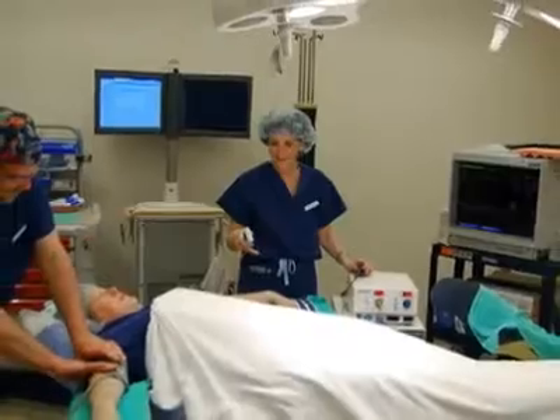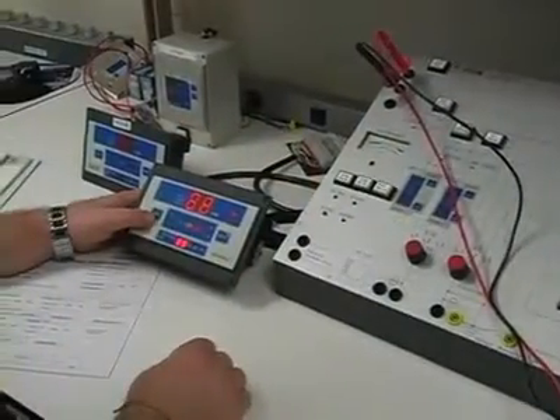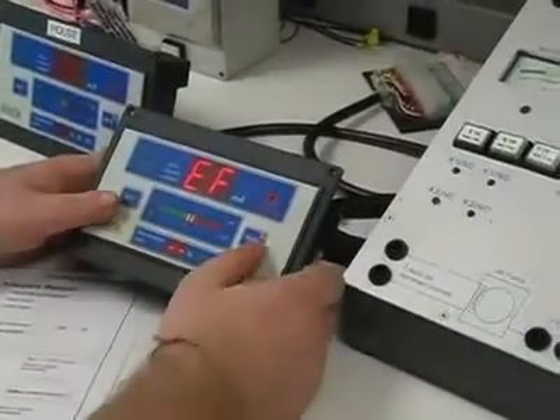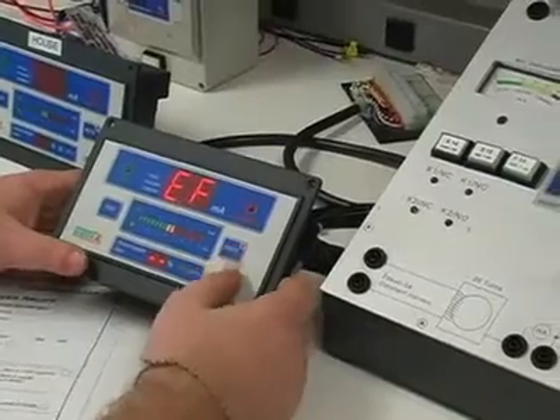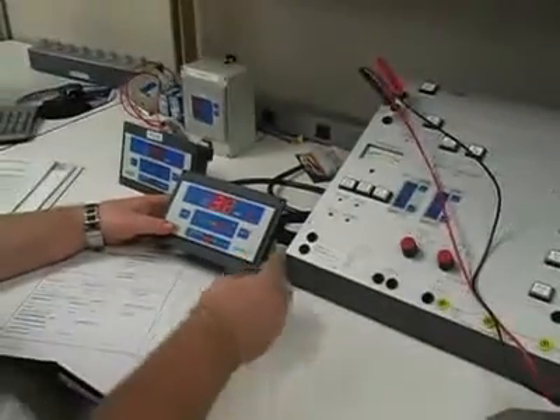As part of the project and before placing the equipment into service, we provided an on-site factory-certified technician to perform inspection and field testing to verify compliance to Article 517 of the National Electric Code and Section 4 of NFPA 99, which is the standard for healthcare facilities.